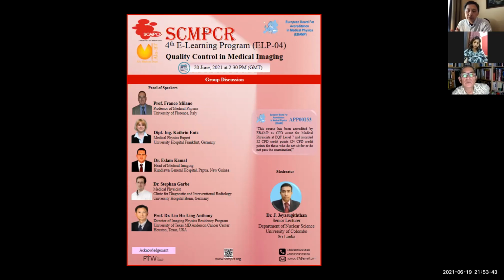But what's most important when using the NEMA method is that you make sure the calibration and the gain are the same between the two images. If you recalibrate the second image, then you cannot subtract the two images. Okay, that's a key point when using the NEMA method.